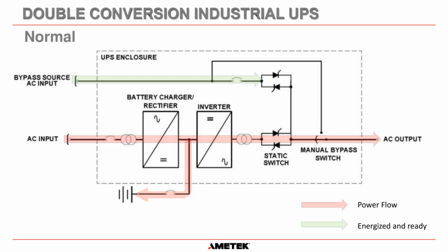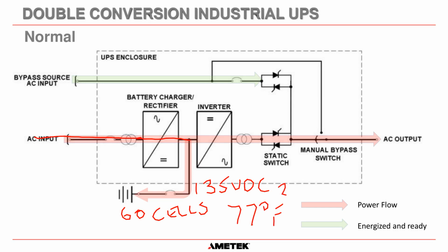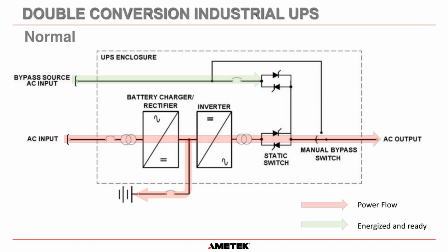And the normal power flow, once again, the red is the normal power flow and green is energized and ready. So once again, the AC input goes into the battery charger rectifier. And we don't have a DC to DC converter in here. We're just taking the AC and turning it into DC. Now, this battery is 60 cells lead acid. So it is going to be charged at 135 volts DC, roughly at 77 degrees Fahrenheit, which is 25 degrees C. Okay? That is for a 60 cell lead acid battery. That is what we are float charging the battery at.